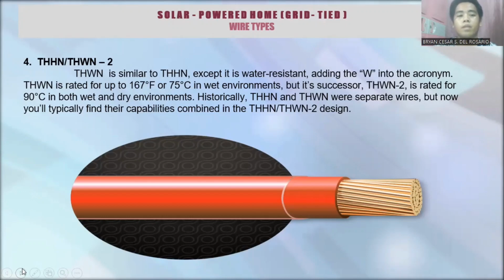THWN is rated for up to 167 degrees Fahrenheit, or 75 degrees Celsius, in wet environments, but its successor THWN2 is rated for 90 degrees Celsius in both wet and dry environments. This is like the upgraded type of the earlier THHN, so it's better to use this one instead.